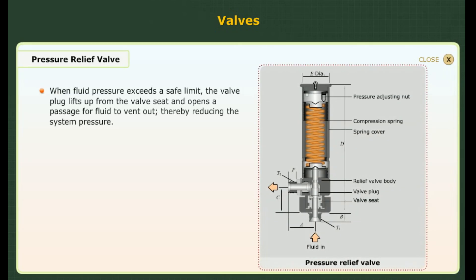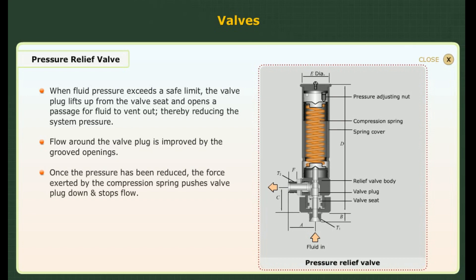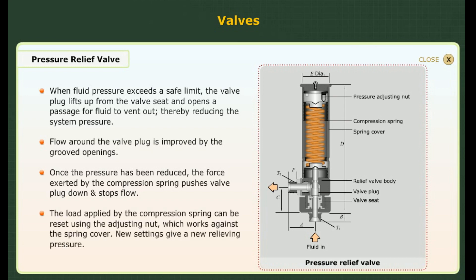Pressure relief valve. When fluid pressure exceeds a safe limit, the valve plug lifts up from the valve seat and opens a passage for the fluid to vent out, thereby reducing the system pressure. Flow around the valve plug is improved by the grooved openings. Once the pressure has been reduced, the force exerted by the compression spring pushes the valve plug down and stops the flow. The load applied by the compression spring can be reset using the adjusting nut, which works against the spring cover. New settings give a new relieving pressure.